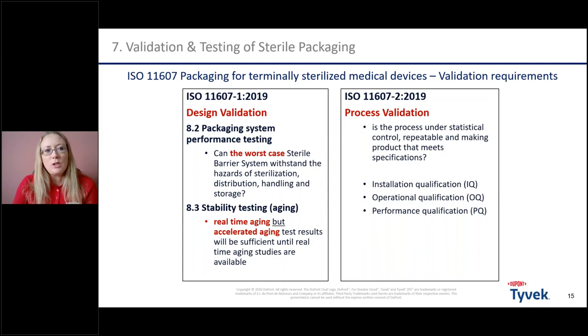After the sealing process definition and packaging design definition, the whole sterile barrier system needs to be tested and validated, according to ISO 11607, packaging for terminally sterilized medical devices. There are requirements in terms of validation. Part two of the standard covers process validation: installation qualification, where you install the equipment and fulfill requirements; operational qualification, where you confirm the parameters and process window; and performance qualification, where you demonstrate reproducibility and repeatability.